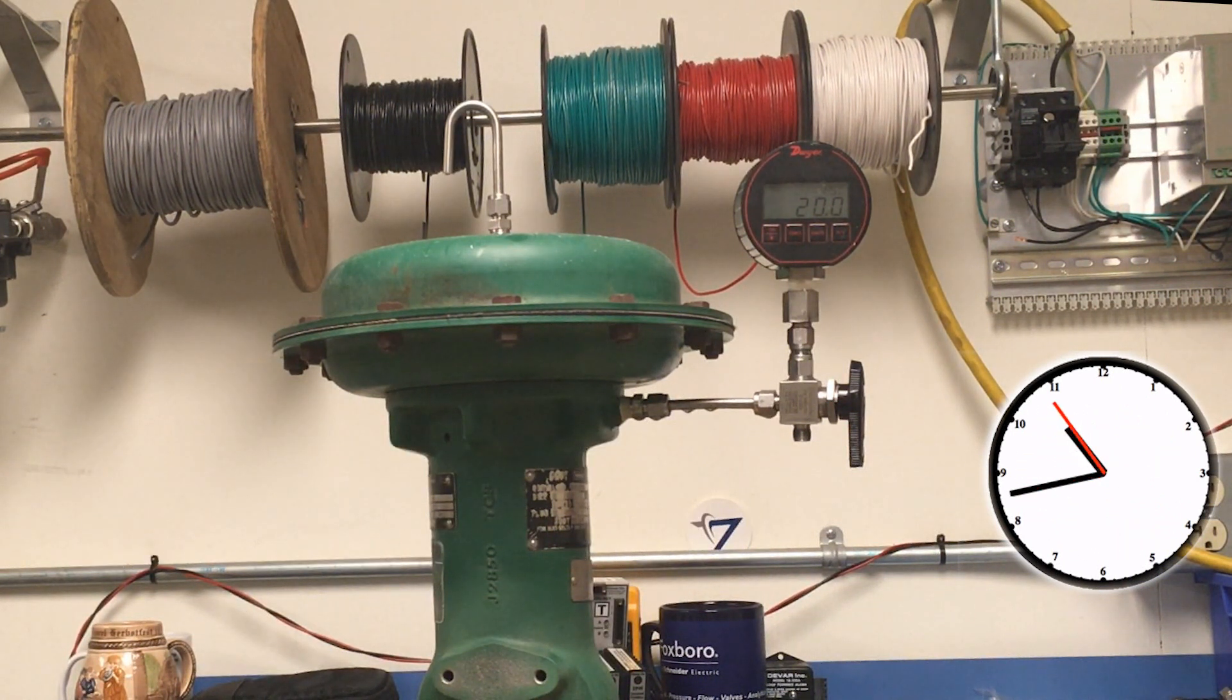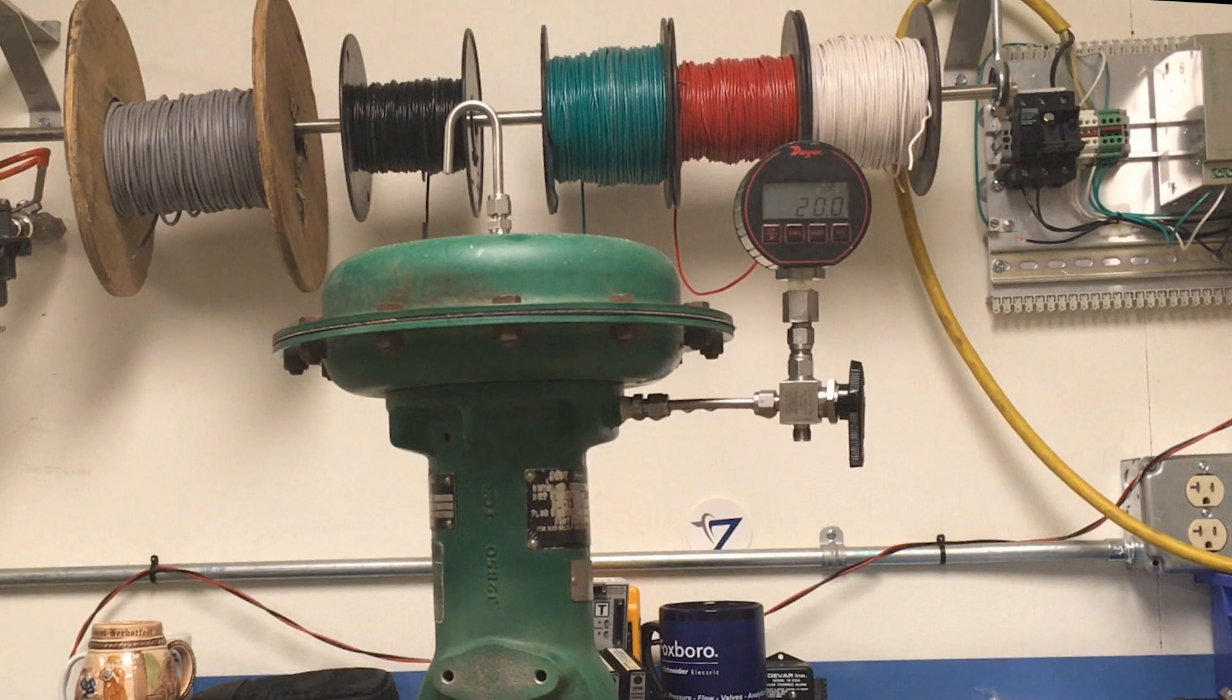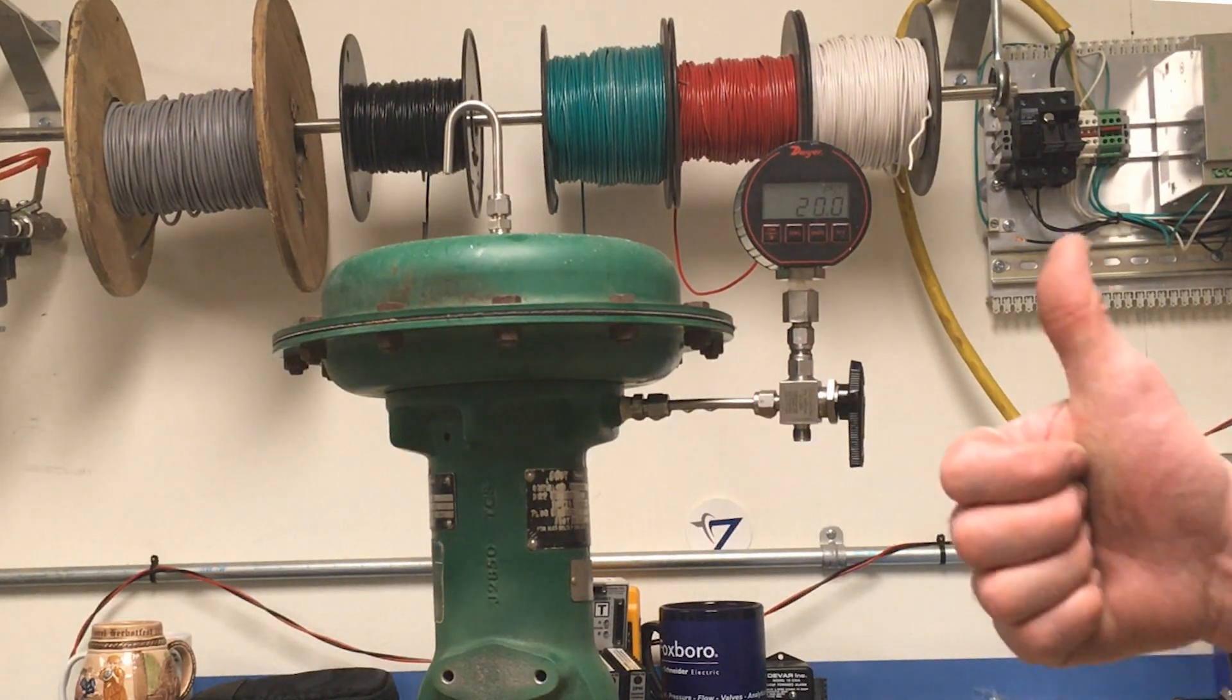When the test is complete, the actuator should not leak air at all. However, as long as the leak rate is no more than 1 psi per minute, the performance should not be affected.